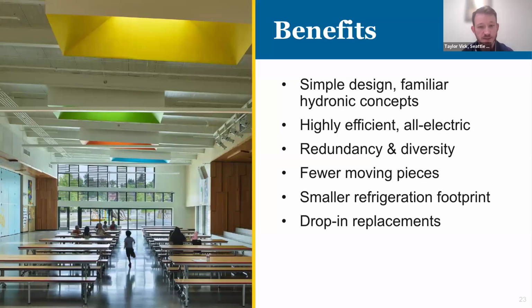So for us, the move towards a simplified central plant was really around redundancy and diversity in the system. We can take a machine offline and still have the rest of the facility operate normally without any indication that there's an issue. So we prefer this over any other type of system, like VRF or distributed heat pumps, just because we get more reliability that way.